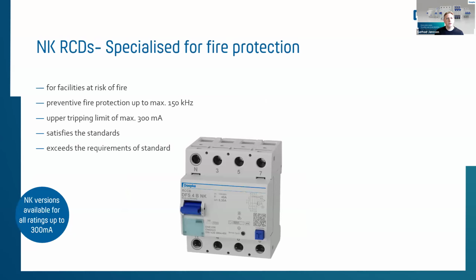From our side, Döpke has specialized products for fire protection. Here you see a type B RCCB for special fire protection applications, which is even better than the standard. The standard goes up to a frequency range of 20 kilohertz, and this breaker, for example, goes up to a frequency range of 150 kilohertz. So we are even above the normal or the required standard. The upper tripping limit is 300 milliamp. The tripping curve or tripping threshold exceeds the requirement of the standards even in the end.